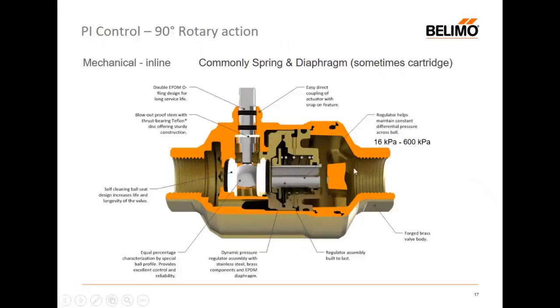We've got the flow moving from right to left. And here we're maintaining a constant delta P in order that we can know exactly how much flow we're going to see to the coil. Any more pressure, any more flow, and the valve will start to close against it just to maintain constant, in this case, the 16 kPa opening pressure of the valve.